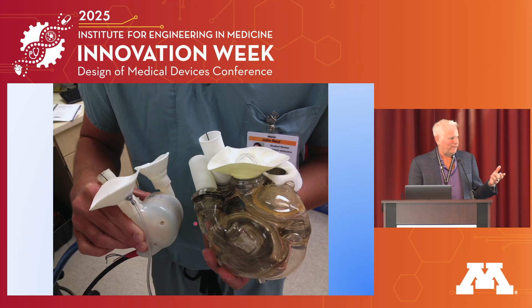It allowed us to do hemolysis tests. And here you can see our BiVACOR pump performs at 12 liters, about like a HeartMate 3, which is the overall class leader. So we do at 12 liters what it does at 5 liters. So the best hemolysis in the field. Why? Because we cut out the diseased heart. We've got so much more room. Our gaps are so much bigger. It also allowed us to characterize hydraulic function and hemodynamic performance. And we did all that. We said, this thing works great.